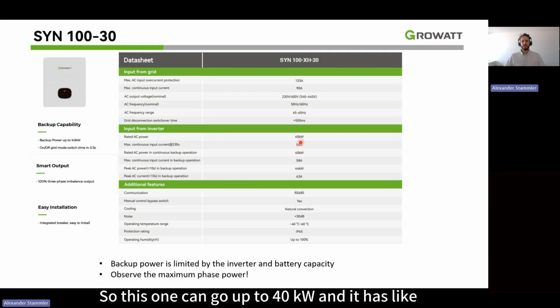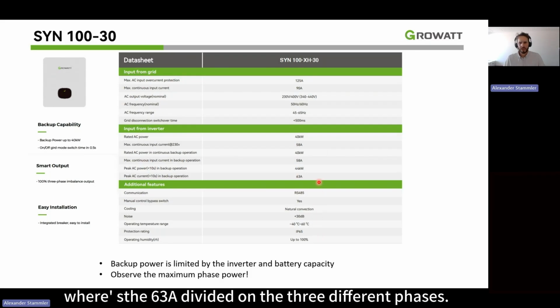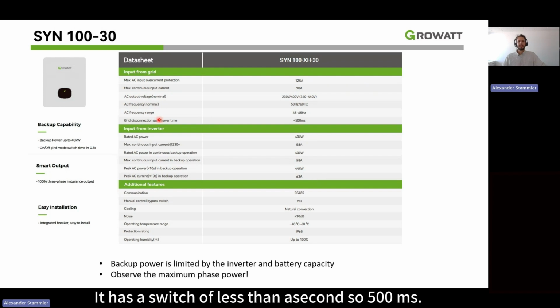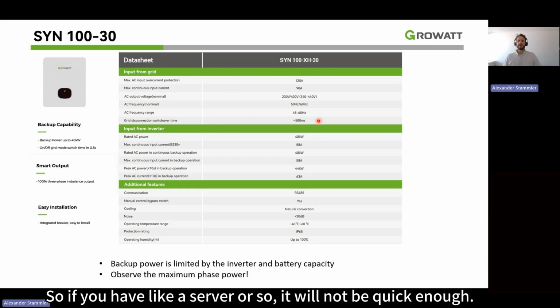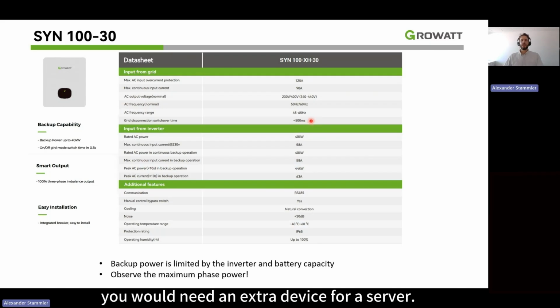So this one can go up to 40 kilowatts, and it has, where's the ampere? Yeah, 63 amperes divided on the three different phases. It has a switch of less than a second, so 500 milliseconds. So if you have like a server or so, it will not be quick enough. You would need an extra device for a server. Maximum continuous input, exactly 90 ampere. Maximum AC input overcurrent protection, 128.